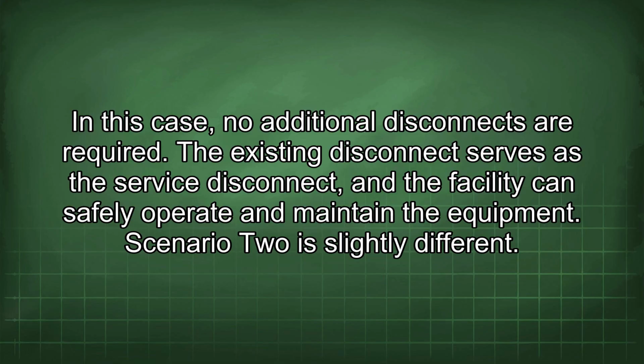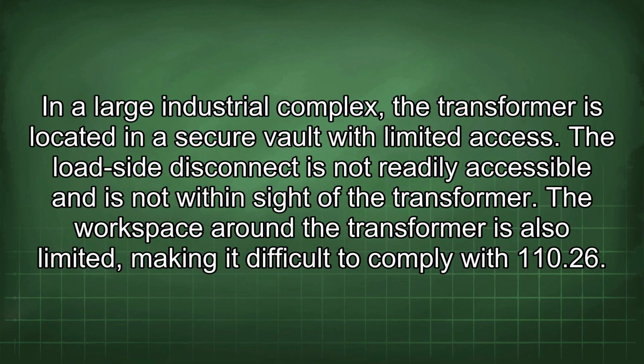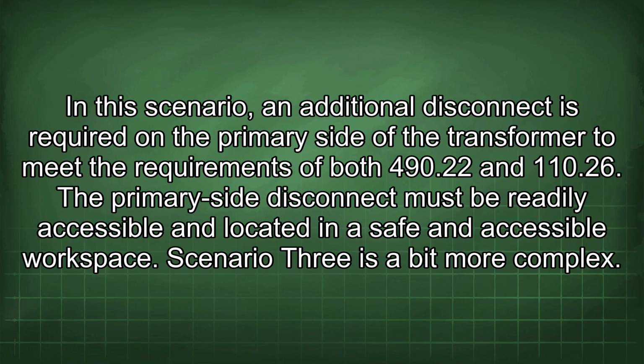Scenario 2 is slightly different. In a large industrial complex, the transformer is located in a secure vault with limited access. The load side disconnect is not readily accessible and is not within sight of the transformer. The workspace around the transformer is also limited, making it difficult to comply with 110.26. In this scenario, an additional disconnect is required on the primary side of the transformer to meet the requirements of both 490.22 and 110.26. The primary side disconnect must be readily accessible and located in a safe and accessible workspace.